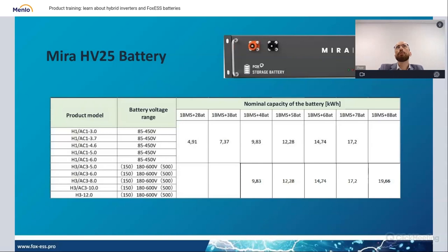Here you have the minimal and maximal stack for those batteries. Those empty places are where that stack will not work. H1 or AC1 one-phase system will not operate above 400 volts. Three-phase system will operate with such voltage, but it needs more voltage for a start to properly operate.